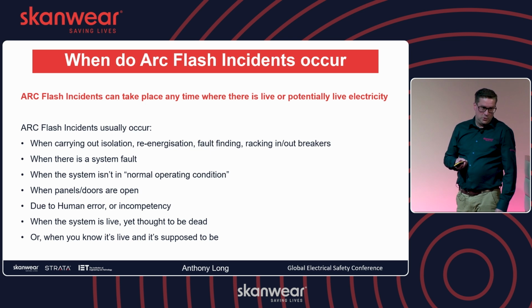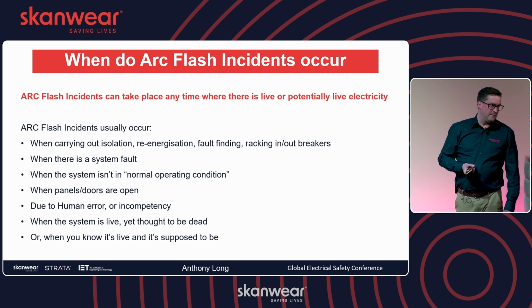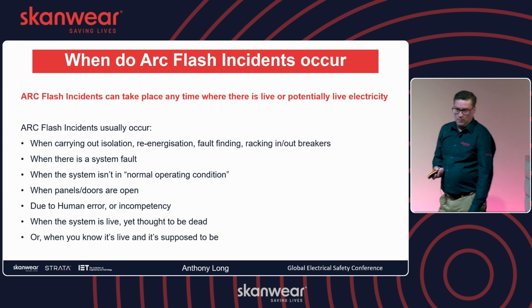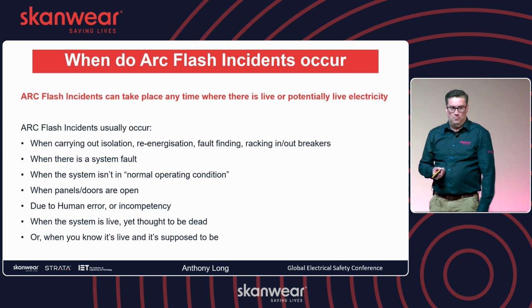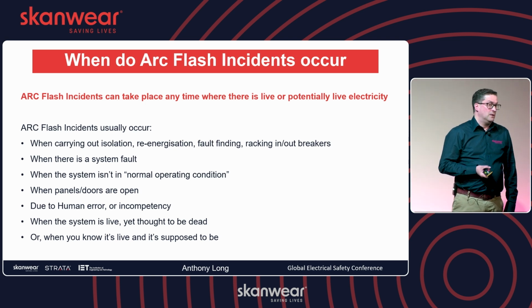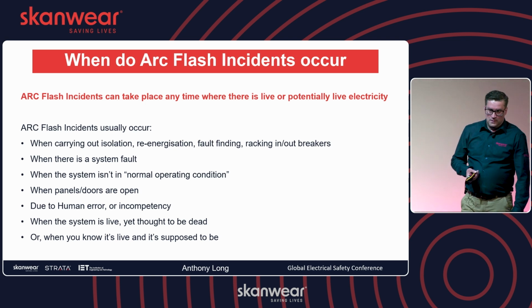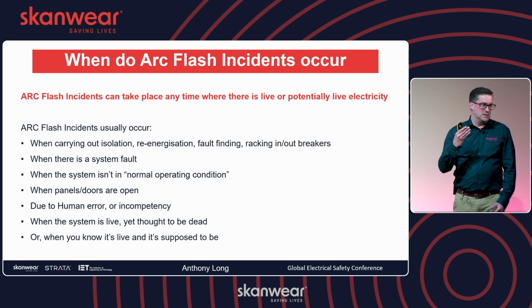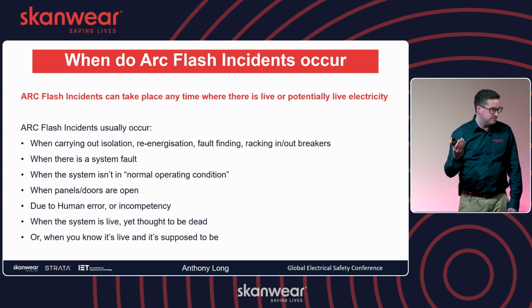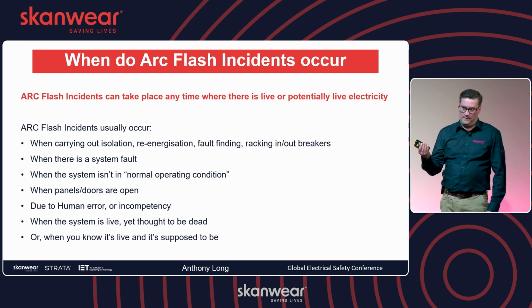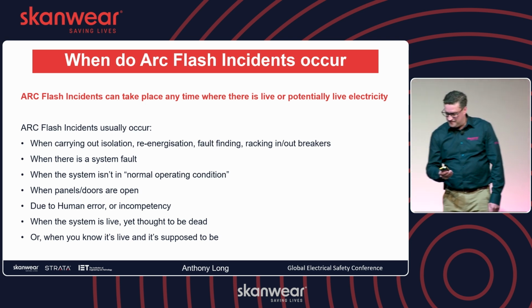I see loads of pictures of panels and doors open, doing fault finding with the system still live, and people wearing polyester or polycotton - slightly better - clothing. You've already got a door open, which acts as an arc flash barrier, the system's live, and worse, you're meddling around when the system's already in fault. You're raising the stakes of an arc flash by a million percent.